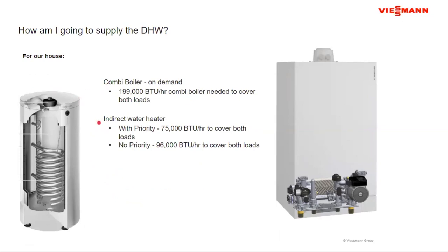If I do an indirect water heater here, and these are actually the loads, not the actual outputs of the boiler, I'm going to need a boiler with an output of 75,000 with priority. If I'm going non-priority, I need 96,000. So in either case, the combi boiler is going to be at least twice the size of the boiler required when I do the storage indirect water heater, because of how the performance numbers and the hot water load requirements change. So when I start to do domestic hot water off of a tank and a boiler, this becomes one of my driving factors in that direction.